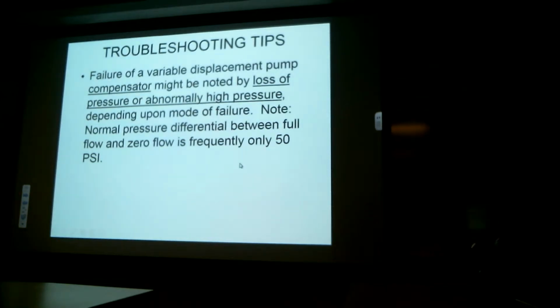Failure of a variable displacement pump compensator might be noted by loss of pressure or abnormally high pressure, depending upon the mode of failure. And it says, note, normal pressure differential between full flow and zero flow is frequently only 50 psi. This makes it really difficult to troubleshoot systems that have got variable displacement pumps. Many of those pumps will push out the maximum fluid flow. They'll be in the full flow position for the bulk of their operating period of time. Only when the last 50 psi necessary to go to zero flow is attained does the compensator finally shift to zero flow, and then all of the flow from the pump is diverted back to the reservoir.